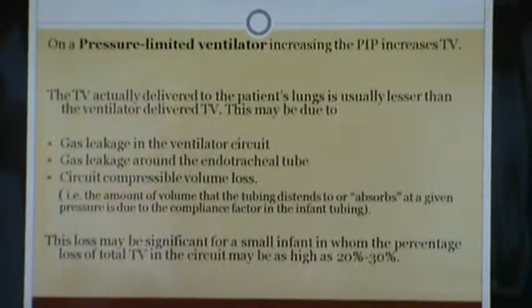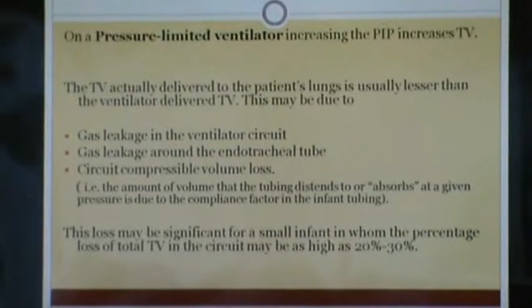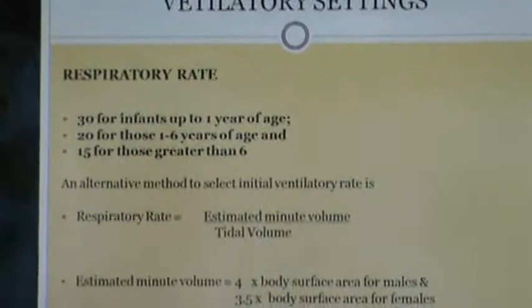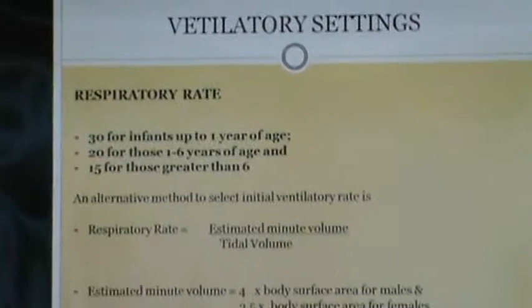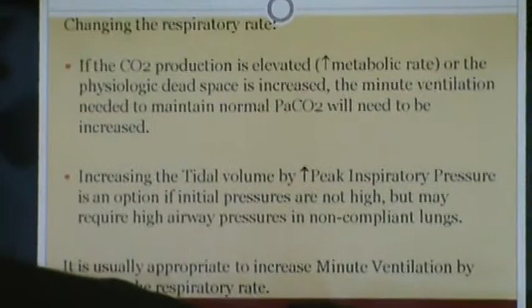On pressure limited ventilation, we can increase the PIP to increase tidal volume, but the only limitation in pediatrics is leakage in the ventilator circuit, then peritubal leak, and compressible volume loss, which is a big trouble mainly in NICUs. Respiratory rate we can choose depending upon the age of the patient. These are the formulas, but it is not always necessary to go with formulas, though you can follow them.